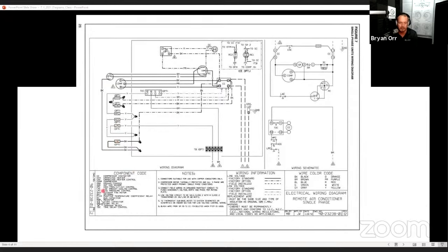Because this is the basics on which you build in order to understand much more complicated schematics and diagrams. And this is the mistake that I think a lot of techs make. Techs jump into complicated schematics and diagrams because they don't need schematics or diagrams on simpler units. You can see it all, you know all the components, so why do you need a schematic, right? And so you're not used to looking at them, but then you end up on the big Munters unit or the big AAON unit or the humidimizer or whatever you're working on that's weird. And now you start trying to read this big complicated schematic and you get overwhelmed. The key to not be overwhelmed is to understand everything that's in them, eliminate what's not there, and then focus on one circuit at a time based on what's happening.